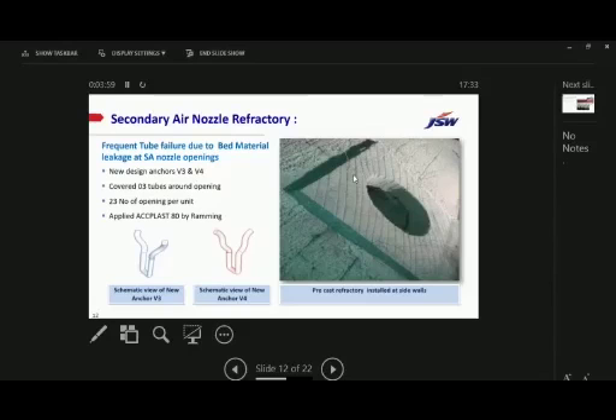Due to the high velocity of air passing through these nozzles, erosion occurred around the nozzle area, and it eroded the refractory and exposed the boiler tubes. When a boiler tube is exposed, due to continued heating from the hot bed material, it also got eroded, and it will create leakages and lead to unit breakdown.